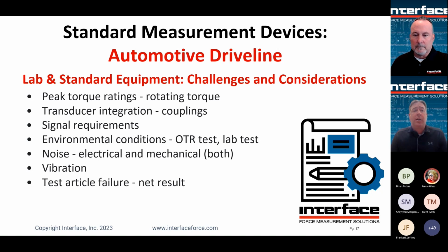Challenges, considerations. A lot of times, dynos can either use axial load cells or they can use rotary torque transducers. And once we start talking about rotary torque transducers, it's very important that people consider and determine what the peak torque rating needs to be for the rotating torque assembly. A lot of times it can be higher than anticipated, and the peak torques can vary widely from the average running torque of the assembly. So things to consider would be startup torques, stopping torques. How fast is that assembly going to spin down? How fast is that assembly going to spin up? And what does the inertial mass do in relation to that peak torque? If it's an instant on motor, for example, and a very high rotating mass, that could really make that peak torque go up very high.